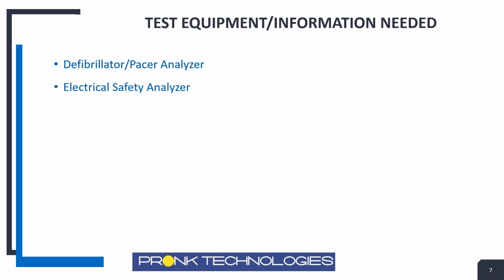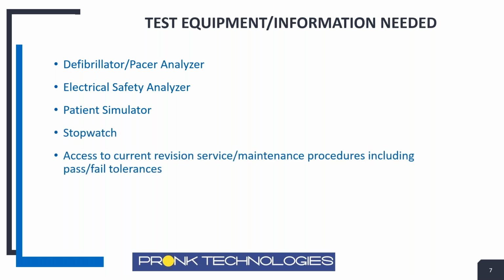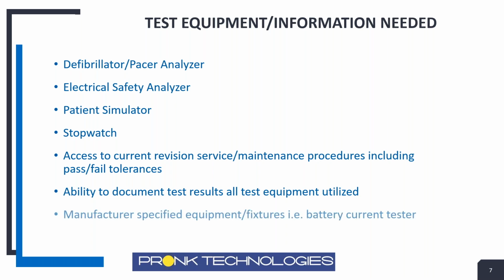So of course, when we're testing these devices, we need a variety of types of test equipment. You need a defib pacer analyzer, if the device has a pacer option, an electrical safety analyzer, simulator, stopwatch, and of course, we need to make sure we have referenced the current service manual for the configuration of the defibrillator. And we need to be able to document all these results. There are some defibrillators that have really specific test fixtures you want to use. They're specific to the device.